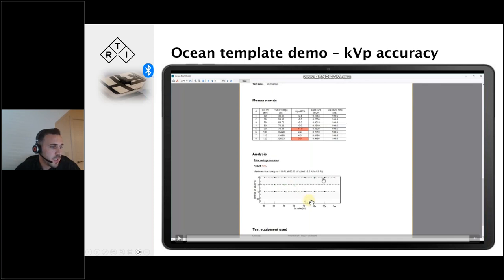You can see above 100 KV it starts to increase towards that 5% tolerance, where it hits 5% there. That's why you typically perform such tests - rather than just at one value, you do a KVP accuracy test across the whole range, so that you know it's consistent and we don't have varying X-ray output at different KVs.